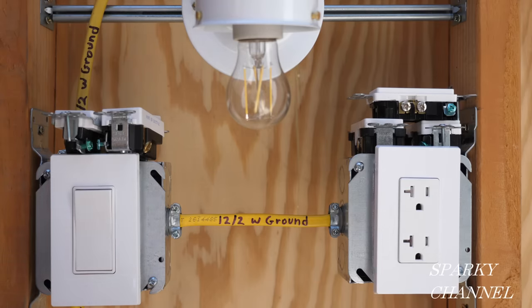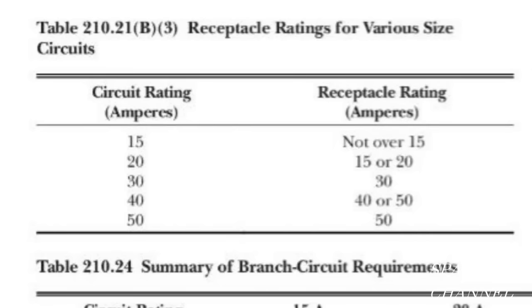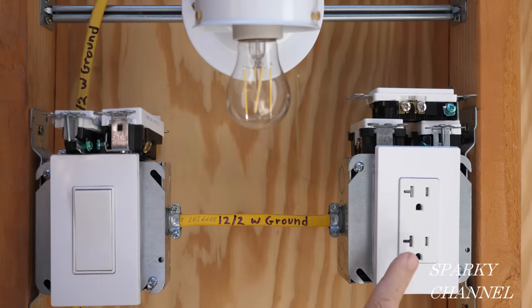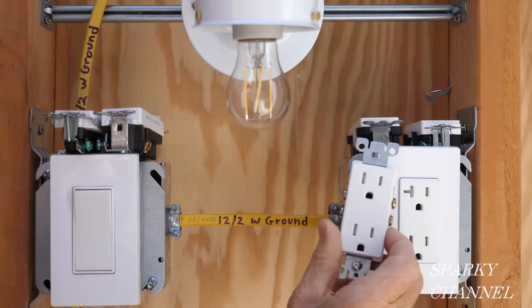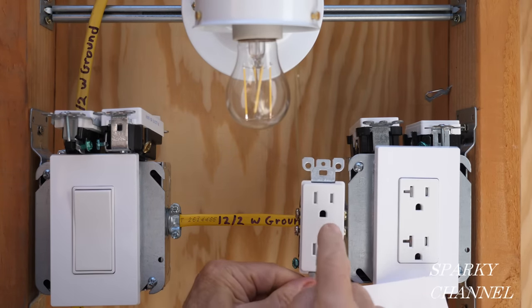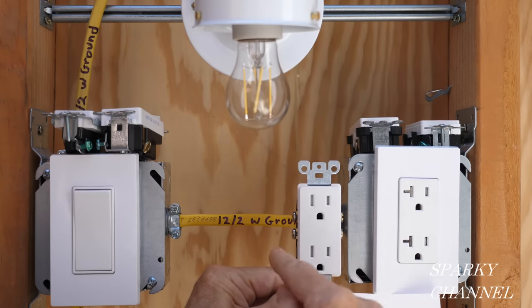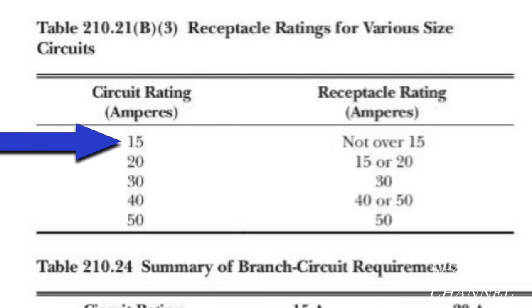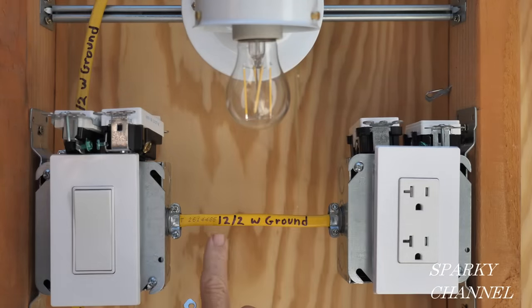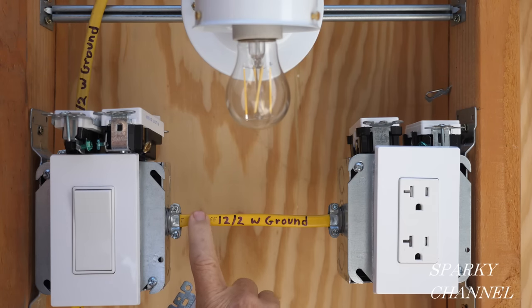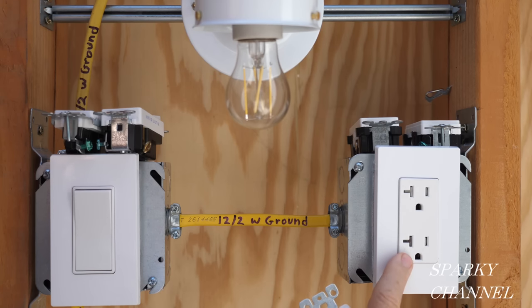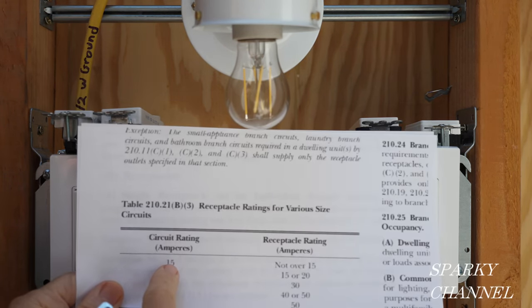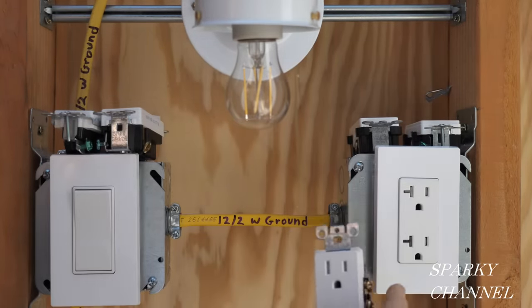The 2020 NEC code, section 210.21B3, covers receptacle ratings for various size circuits. This is a 20 amp receptacle and this is rated at 15 amp. The table shows circuit rating in amperes: when the circuit is 15 amps, you're not to use a receptacle over 15 amps. So if this was a 14-2 with ground on a 15 amp circuit breaker, I could not use this 20 amp receptacle.